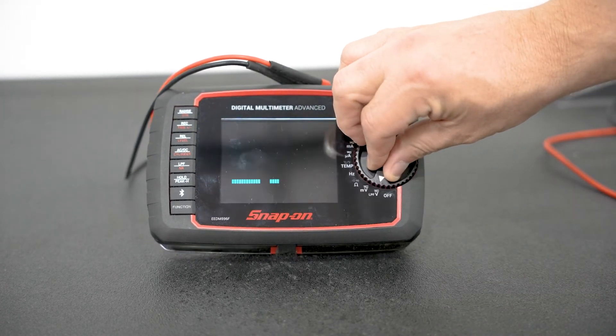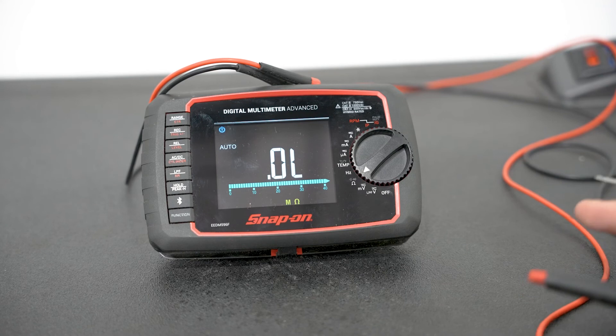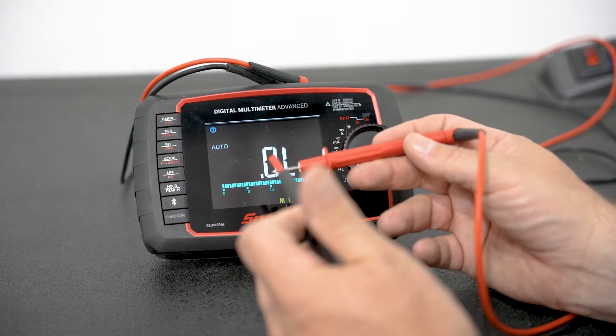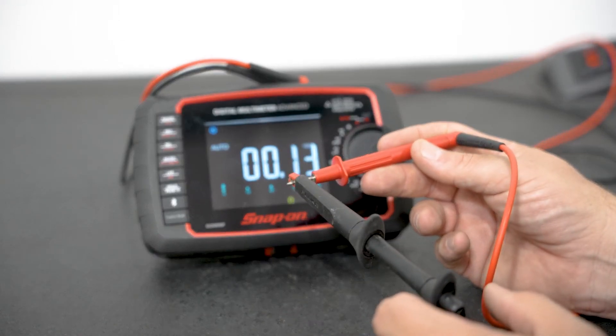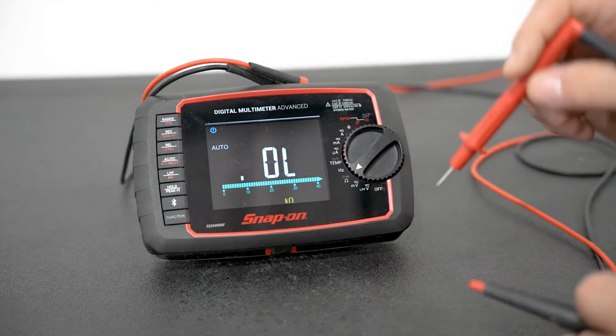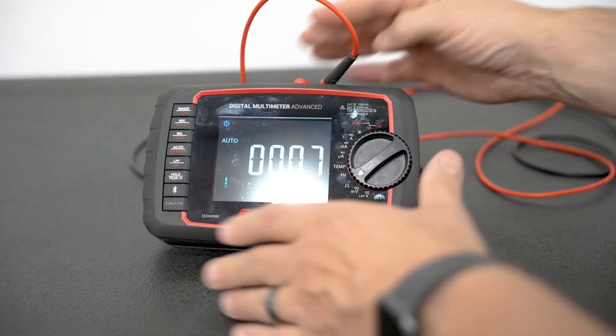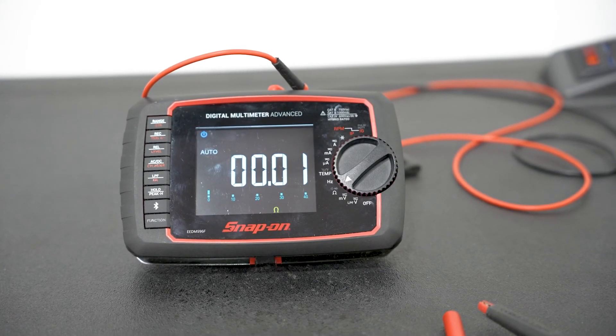We're going to turn on to the ohms setting for right now. As soon as you turn it on to the ohm setting, you can see it goes into an open loop — with it being an open loop, you have nothing connected to give you resistance. If you take the two meter leads and put them together, you can see that your resistance has changed. This is a good way to verify that your meter is set up and working. If I think I might have a bad cable or harness, I can connect it right into the COM port, and now my meter is reading that loop so I can verify that my meter lead is effective and good to use.